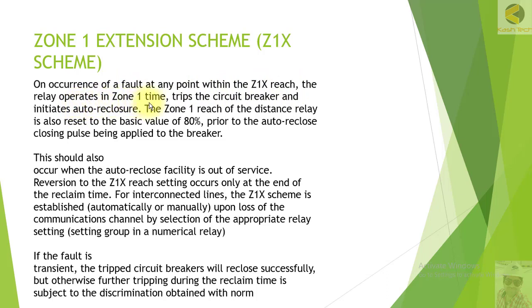The relay operates in Zone 1 time, trips the circuit breaker, and initiates auto-reclose. The Zone 1 reach of the distance relay is also reset to the basic value of 80% prior to the auto-reclose closing pulse being applied to the breaker. So Zone 1 is always extended in normal healthy condition to 120%. When the relay trips and the auto-reclose functions, it sends a pulse to the relay resetting Z1X from 120% back to 80%. If the fault persists, the relay will work as a normal graded zone scheme in the second attempt.